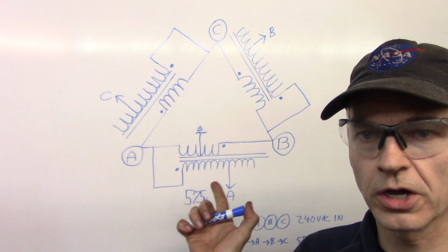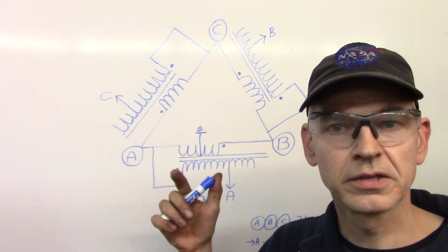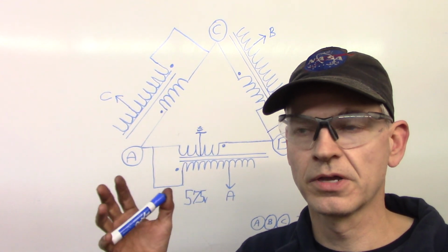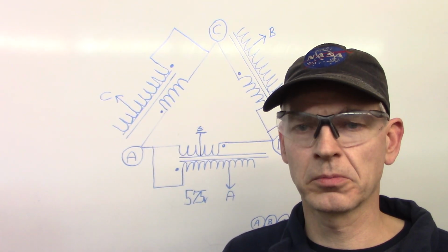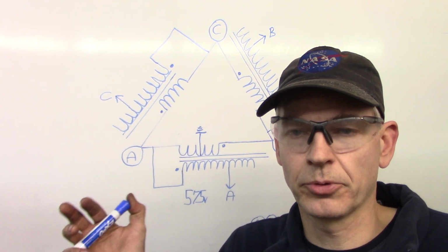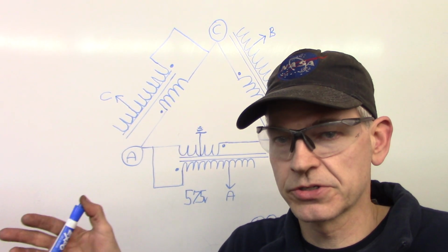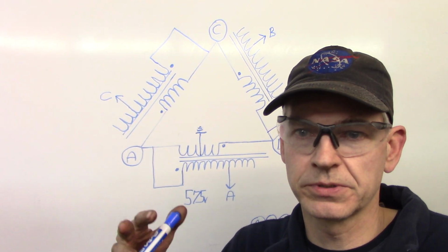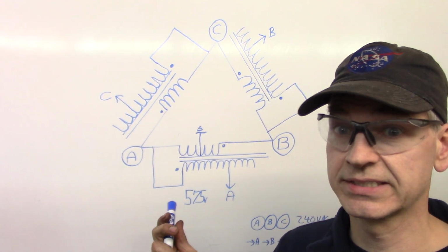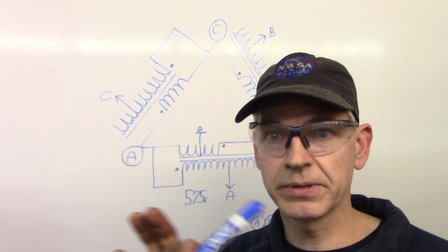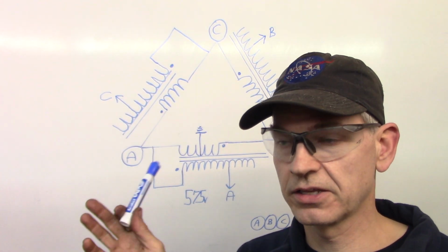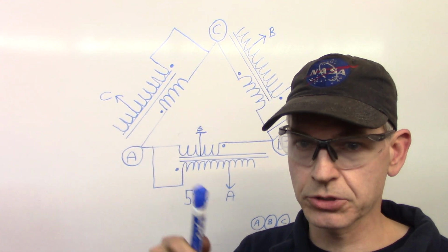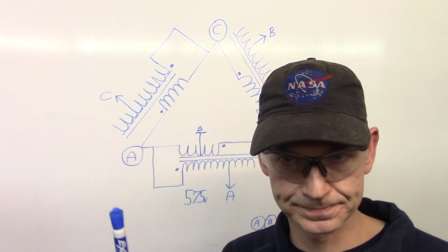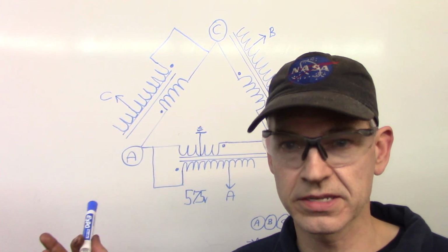Because this is no longer an isolation transformer, people say you've got to use a Y-connected transformer because then you can ground the center point and have a new ground, since you're inventing a new power source with an isolation transformer. This is not that. So don't worry about being delta—it's grounded at the pole, it's grounded multiple ways.